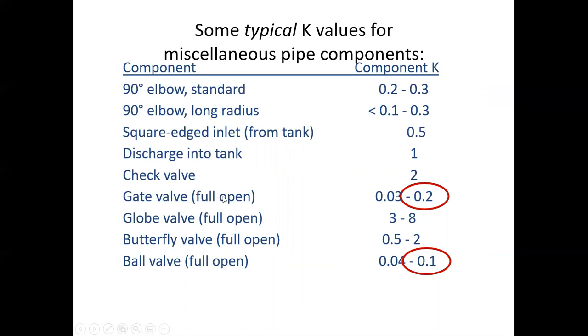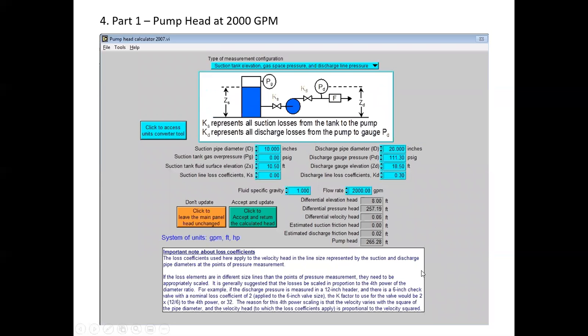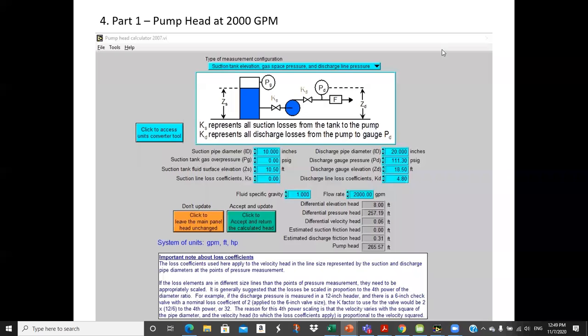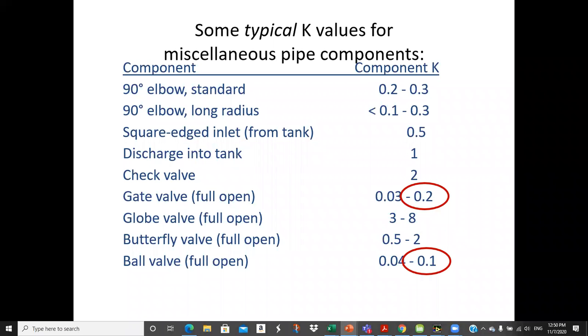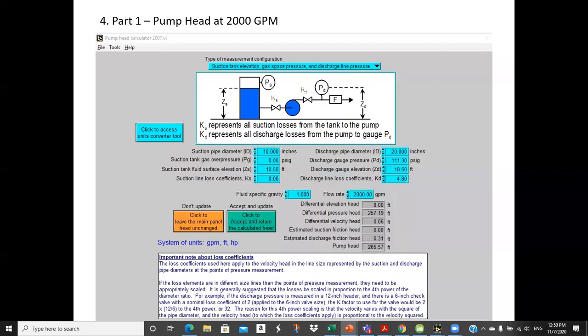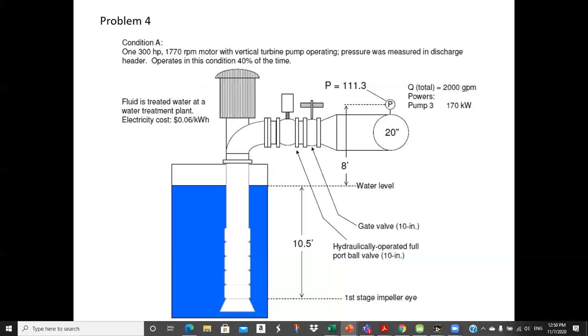Okay, so I look at my gate valve in the fully open condition, it's 0.2, and the ball valve is 0.1. And the pump head, well, just a second, I'm going to pause for just a second here. Okay, so here we are calculating the pump head for the case of 2000 GPM. And like we had said previously, these are the values taken as the loss coefficient: for the gate valve full open use 0.2, for the ball valve full open use 0.1. And you do need to note that if we look at the diagram here, this pressure is measured in a 20-inch pipe, and these are 10-inch gate valve and ball valve.